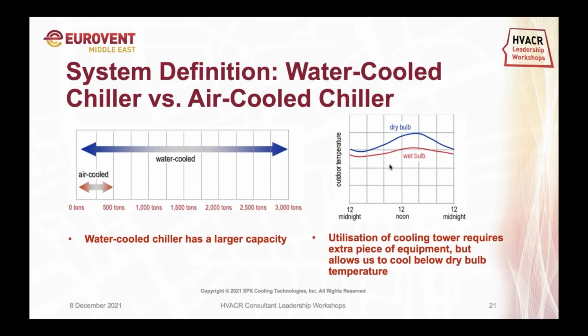The second most important thing is that the air-cooled chiller relies on the dry bulb, and we all know how high the dry bulb is in this region, while the evaporative cooling system depends on the wet bulb. The difference between these two, at peak summer, can be more than 10 to 12 degrees, which we will go into detail on in future slides, covered by my industry colleagues.